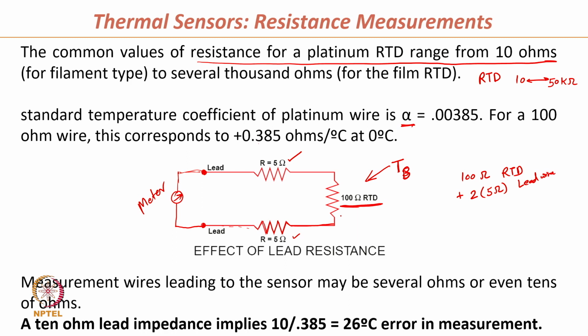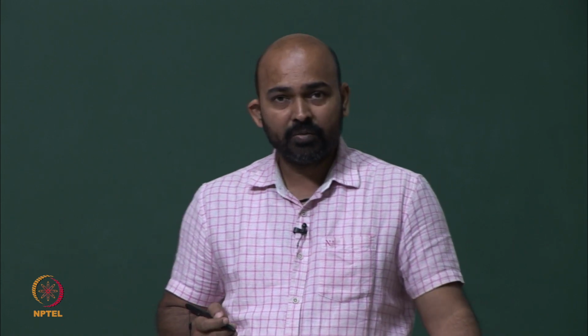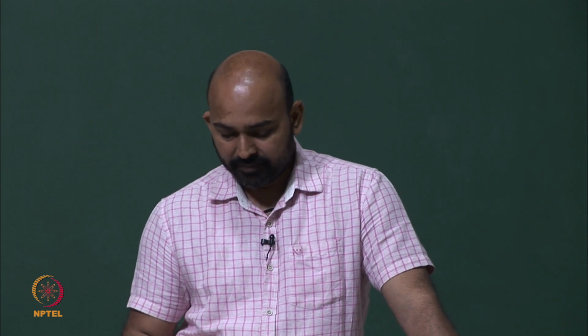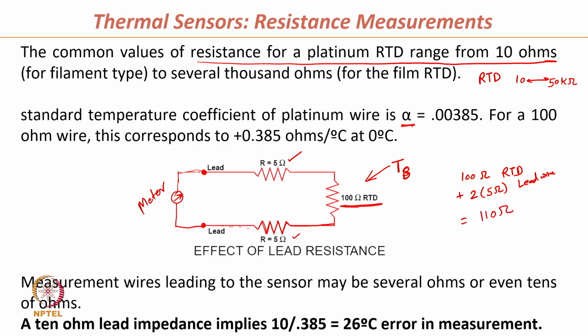So, actually we have a RTD of 100 ohm, but effectively when we join this using lead wires, the total resistance is not 100 ohm, which is now 100 plus 10 ohm, which is 110 ohm. So, because of these extra lead wires, now my meter is not reading 100 ohm, but it is actually reading 110 ohm. So, this measurement wires leads to the sensor maybe several ohms or even tens of ohms. Depending upon the value of these lead wires, this reading can be even more degraded.